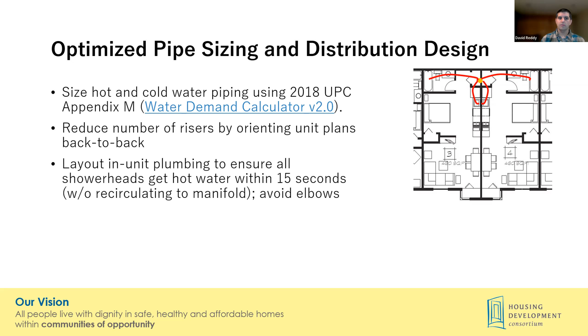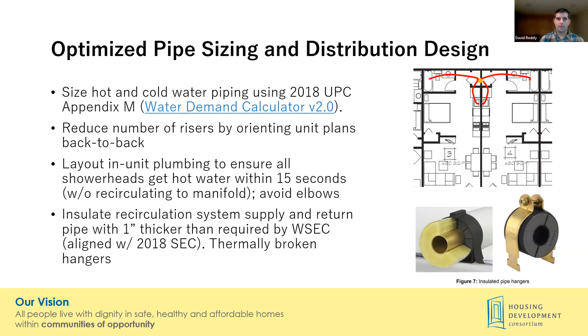And then lastly, to insulate pipes with more insulation, we're adopting what is already in the Seattle Energy Code, with 1 inch more insulation than what has been required in the past. Again, to reduce hot water loads, all these things address that big number Alistair mentioned, up to 50% of the energy being lost through the circulation system, and we're trying to address that problem.